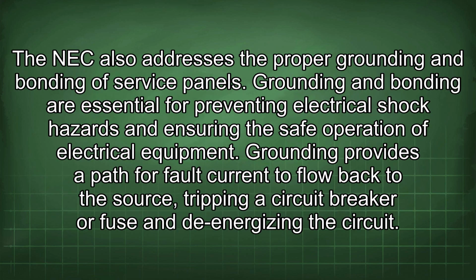The NEC also addresses the proper grounding and bonding of service panels. Grounding and bonding are essential for preventing electrical shock hazards and ensuring the safe operation of electrical equipment. Grounding provides a path for fault current to flow back to the source, tripping a circuit breaker or fuse and de-energizing the circuit.